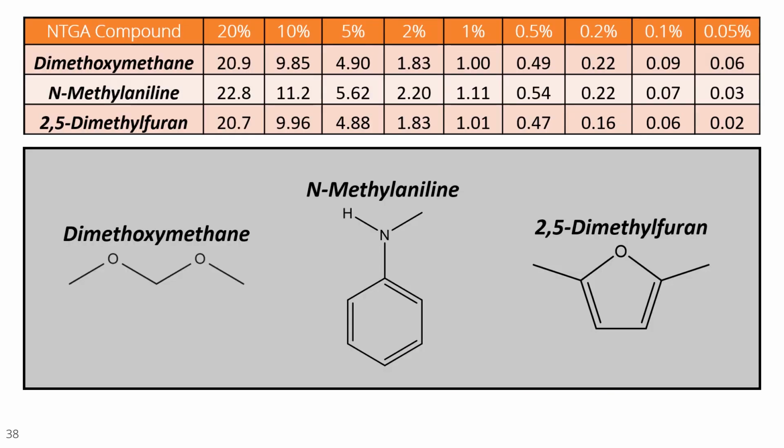And these are the results for the samples we did at an extended concentration range, so from 20% down to 0.05%. And once again, when you take a look at these numbers, we're doing very well, getting the results that we expected, especially when you go to the lower concentration ranges down here. You can see that we're pretty close.